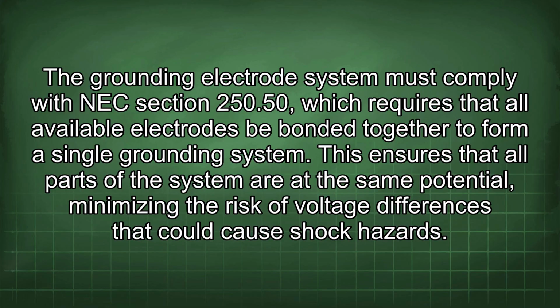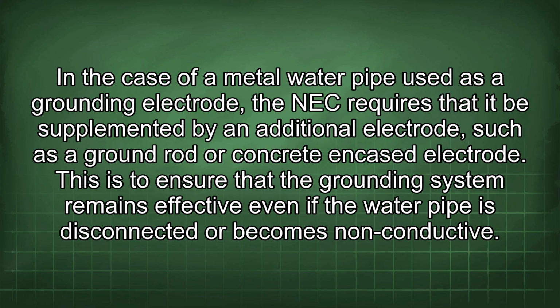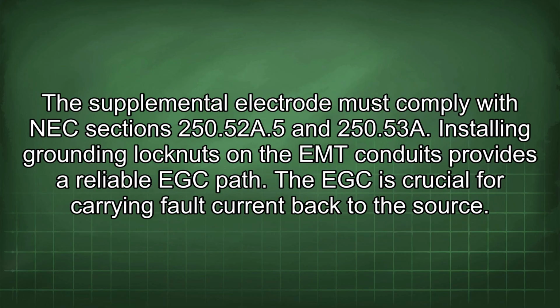This ensures that all parts of the system are at the same potential, minimizing the risk of voltage differences that could cause shock hazards. In the case of a metal water pipe used as a grounding electrode, the NEC requires that it be supplemented by an additional electrode, such as a ground rod or concrete encased electrode. This is to ensure that the grounding system remains effective even if the water pipe is disconnected or becomes non-conductive. The supplemental electrode must comply with NEC sections 250.52(A)(5) and 250.53(A). Installing grounding lock nuts in the EMT conduits provides a reliable EGC path.